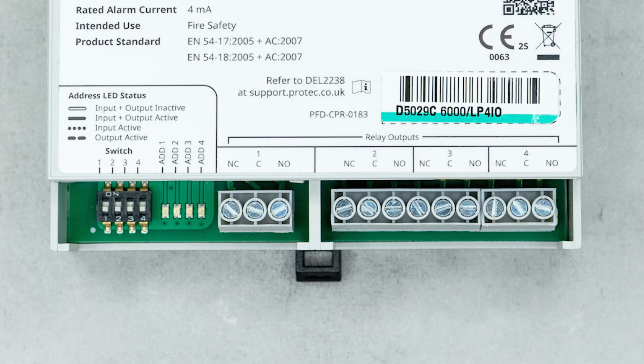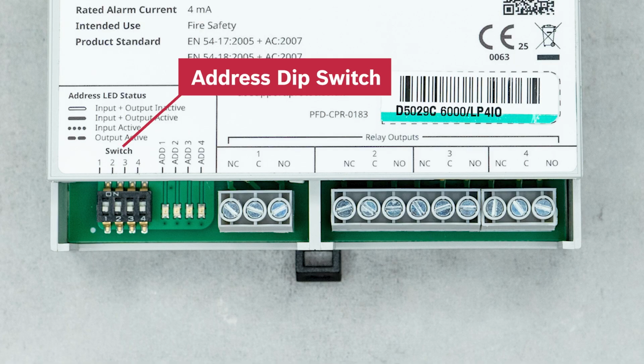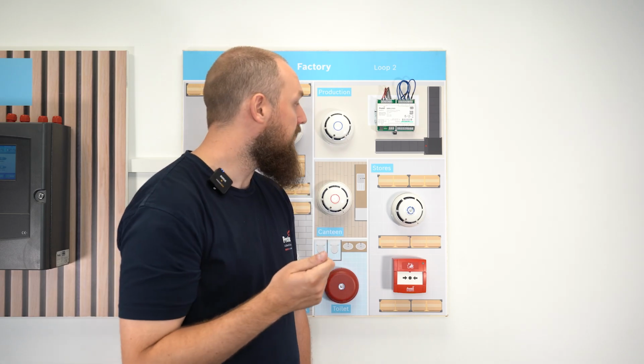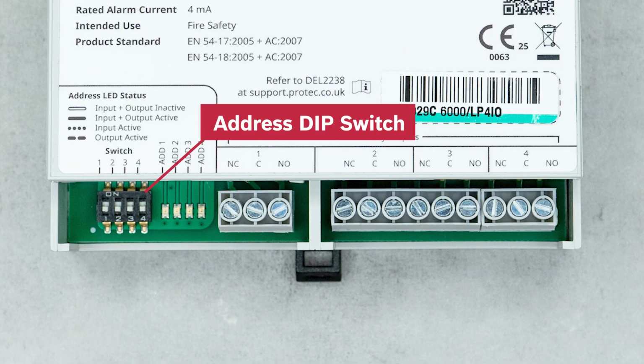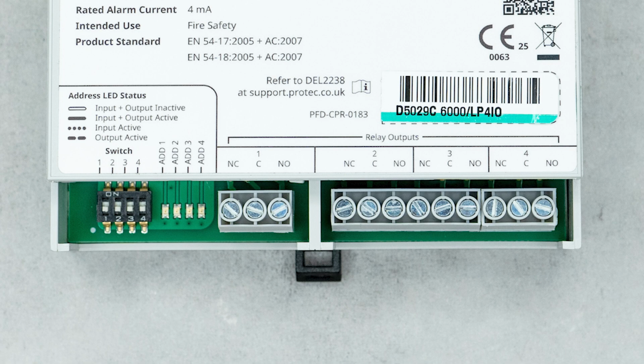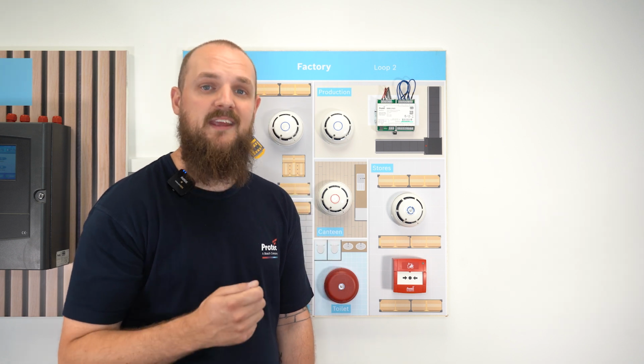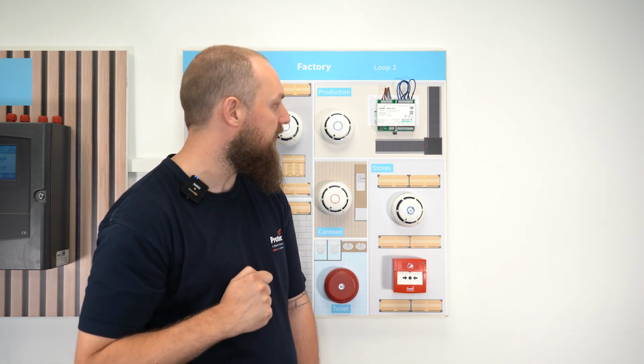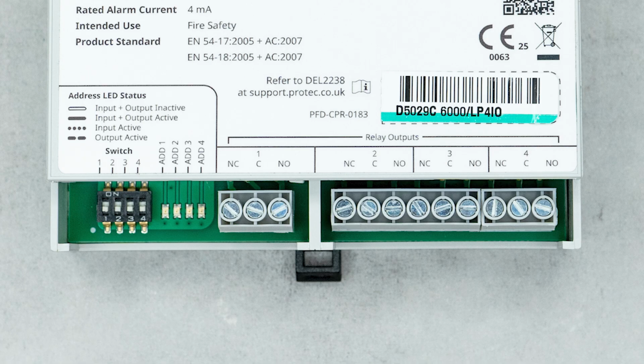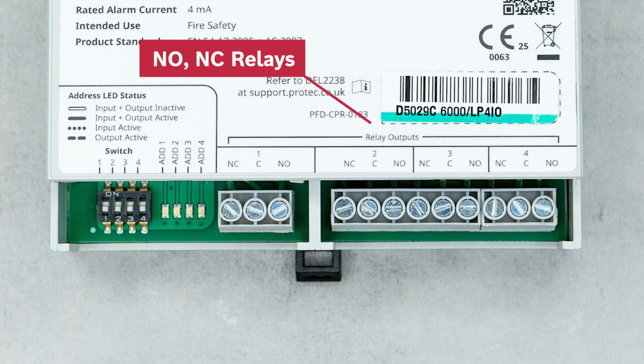On the bottom row we have firstly the 4 address status dip switches. Each of these dip switches is allocated to one of the 4 addresses on the I/O unit. This allows us to enable or disable each address individually. After that, we have 4 status LEDs. These LEDs are there to show whether each input and output for each address is active or inactive at any specific time. Lastly, we have our 4 normally open, normally closed relays. These are 24 volt DC operated relays.